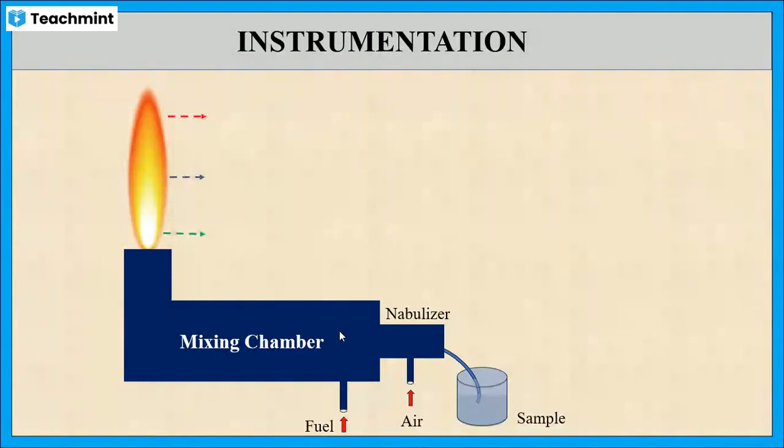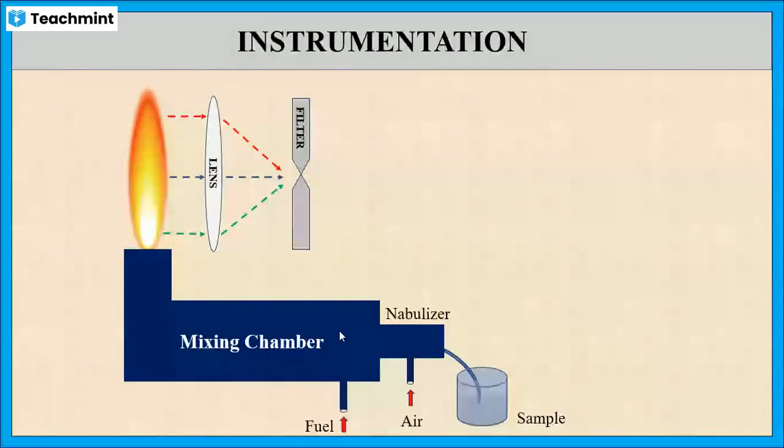These radiations are passed through the lens, these are focused into the slit of the filter. The filter allows a particular wavelength of radiation. For example, if we are interested to measure sodium, then wavelength will be set at the filter as 589 nanometer. Then the emitted radiation is received by the photo detector that converts it into electrical signal.